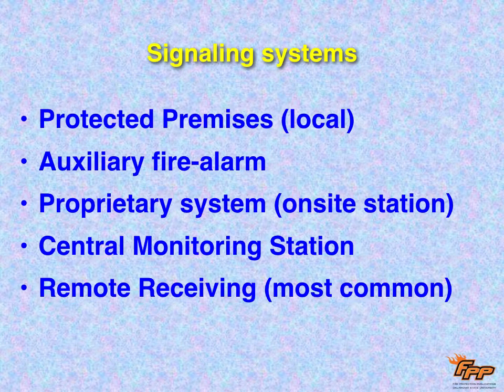There are different kinds of systems. There's protected premises, which is just local. The alarm's only going to go off there in the building. It's not going to notify the fire department. You've got to call 911. There's auxiliary fire alarm systems. There's proprietary. Proprietary systems are where you have 24/7 security on site. They're allowed to have a system where the alarm goes to the room where someone is supposed to be monitoring the system 24/7. Then they can send security or check into it, and then they call 911.